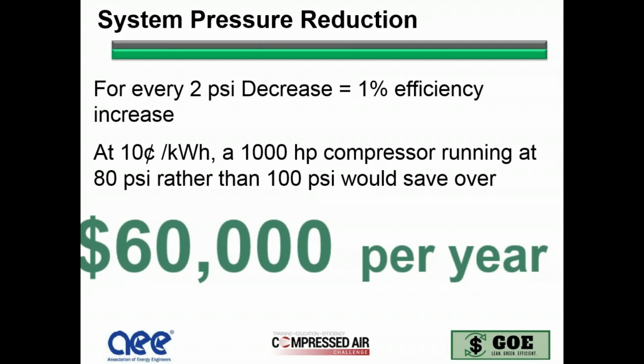Either way, it's a good opportunity to look at. And one of the reasons you want to look at what the actual requirements and your demand are is to see if there's the opportunity and the possibility to do this pressure reduction in a system. Now, again, you have to be aware of what's happening in the system. You can't just lower pressure because that'll affect production. But the real key is understanding what you need to do to be able to lower that pressure.